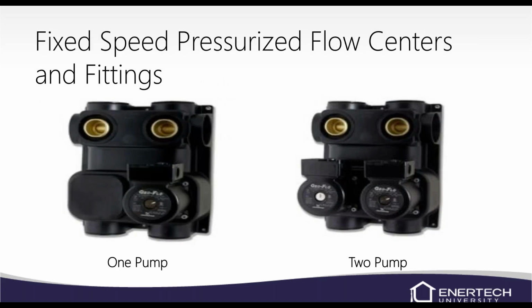We have fixed speed pressurized flow centers. We have 1 pump, 2 pump, 3 pump, 4 pump flow centers, just depending on the size of the unit. Usually a 1 pump will go up to about 4 tons, obviously depending on the length of their loop field, but usually it's right about 4 tons. We usually got to step it up to a 2 pump right about 5 ton. And the 2 pump is usually pretty good for up to maybe 7 tons or so. Then from maybe 7 to 10, maybe a 3 pumper, and then anything over probably 10 ton, if you had a fixed speed pressurized flow center, it would be probably a 4 pump.